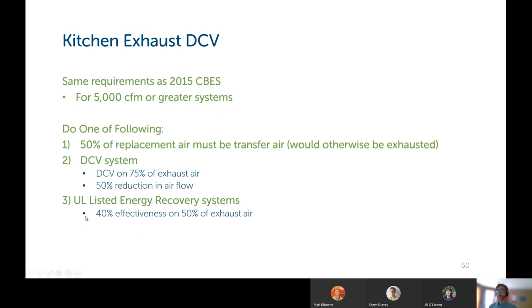The third option is an energy recovery system that's UL listed. That would be 40% effectiveness on at least 50% of the air that you are exhausting. Those are the same requirements as the 2015 code. Question? Yep.